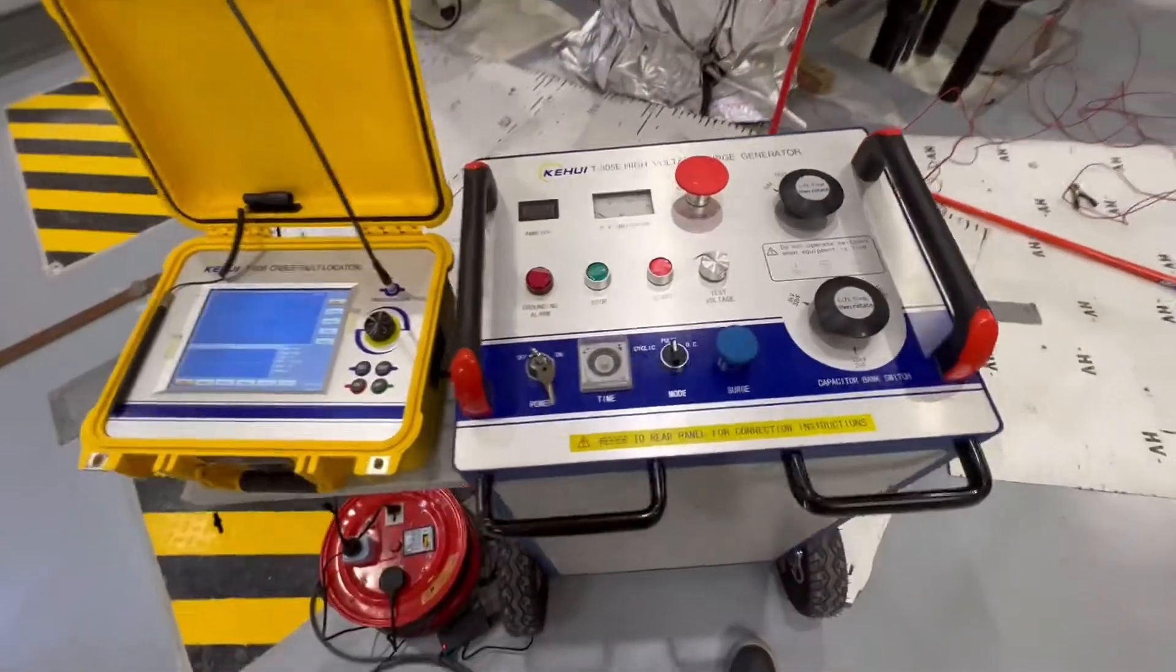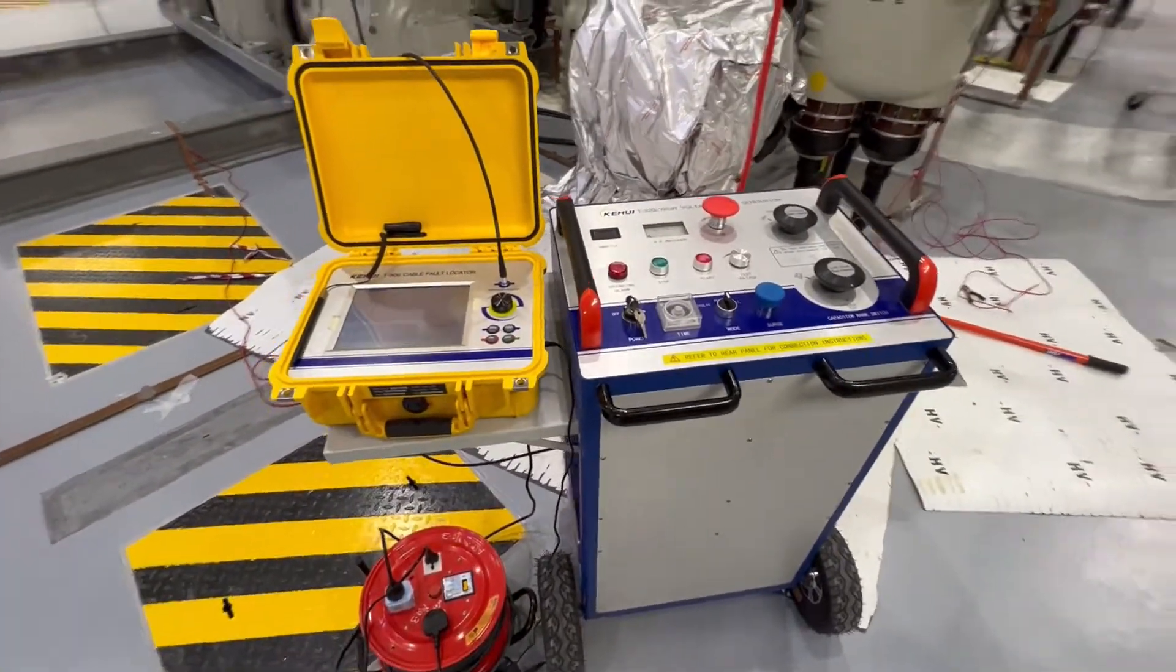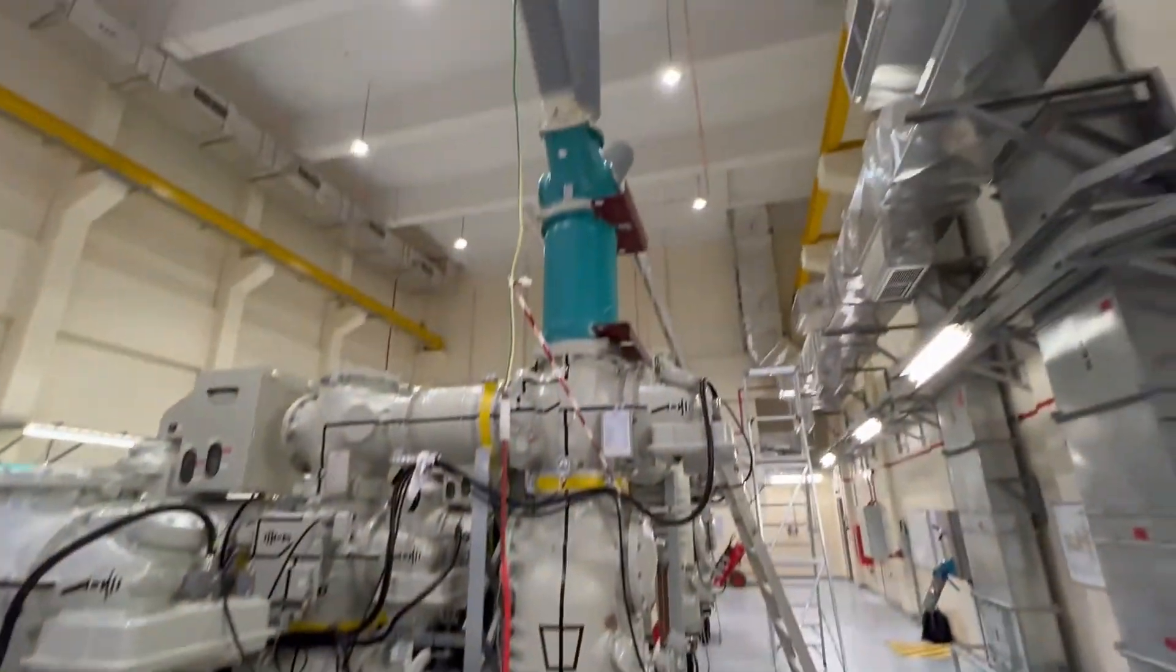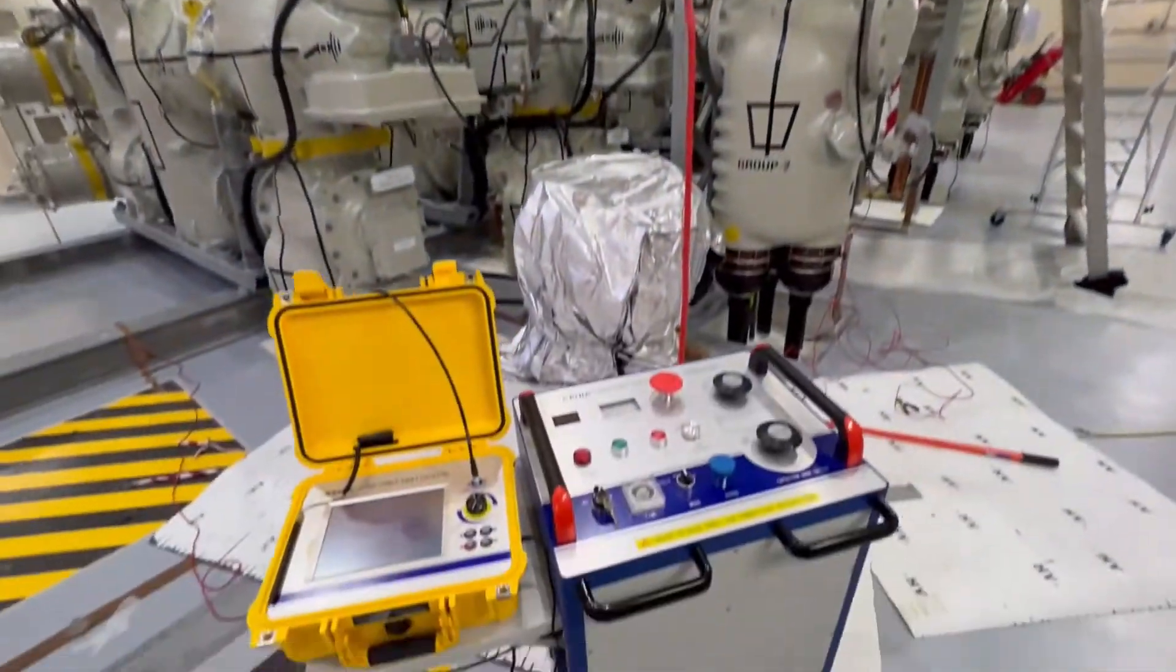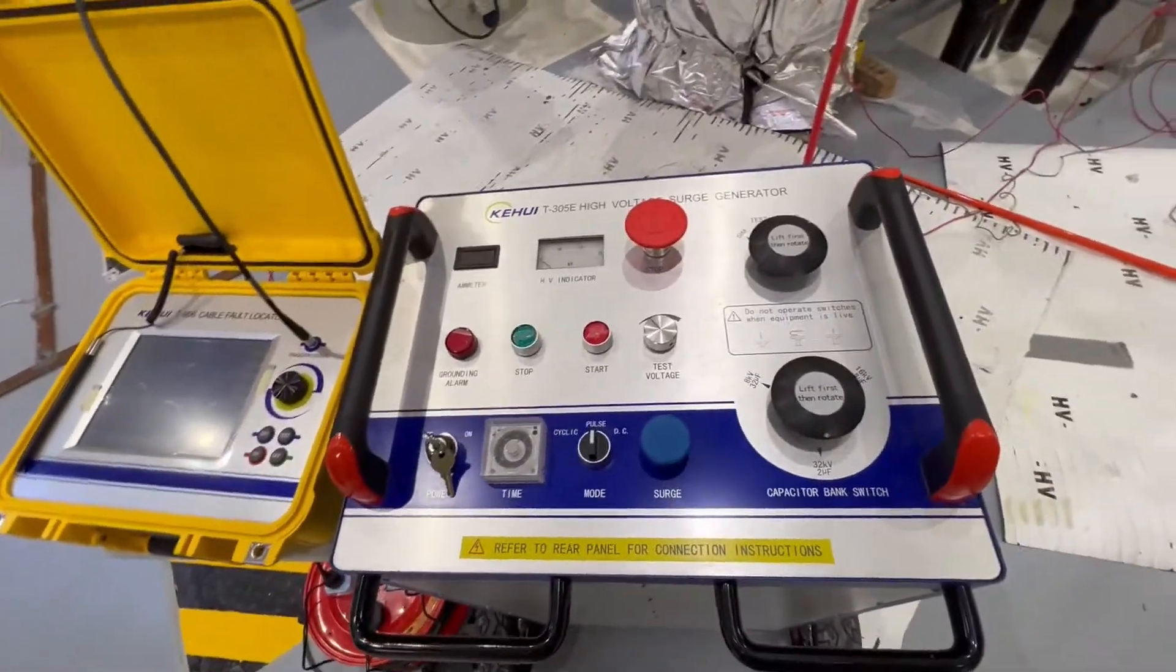Hi, this is Kehui cable fault location equipment. You are seeing that the surge generator is connected to the fault locator, and testing is going on for a 32 kV cable which is one kilometer or 1.1 kilometers, 100 meters long.